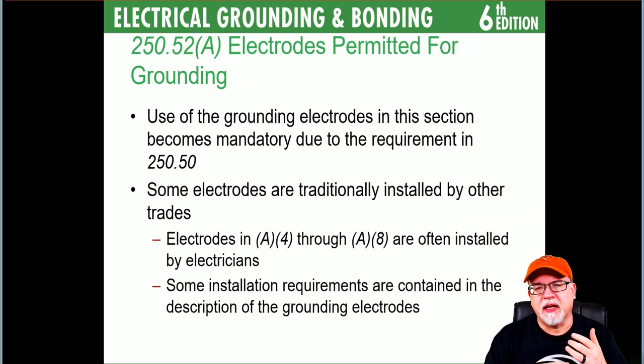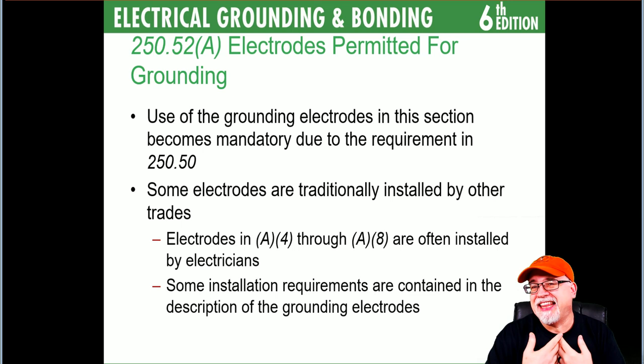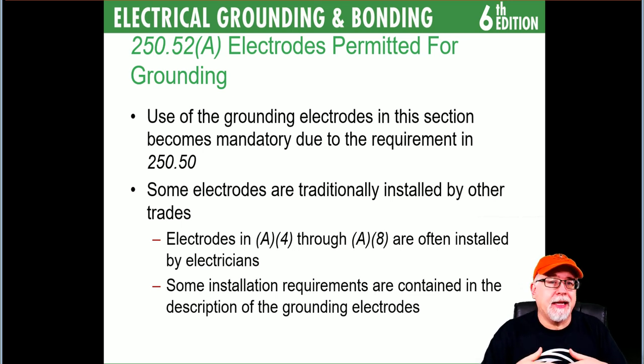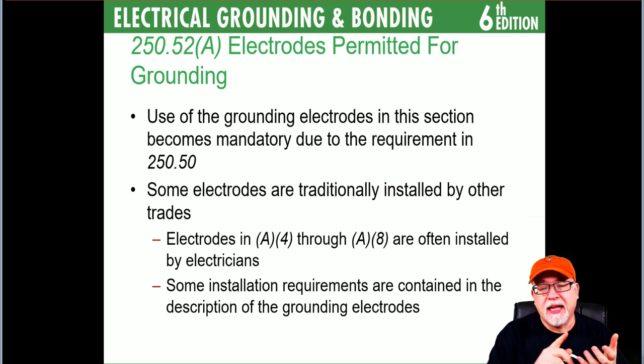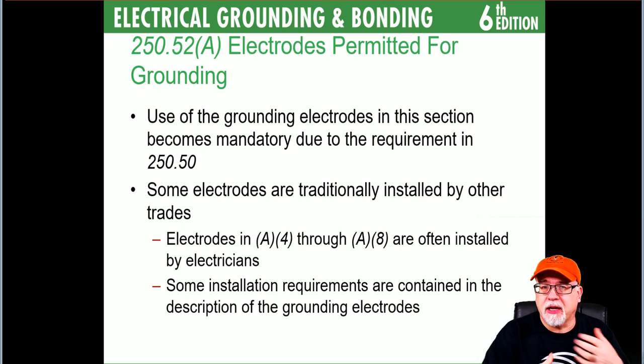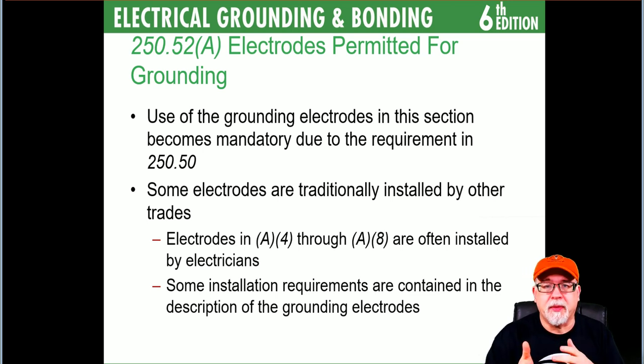Electrodes permitted for grounding: use of grounding electrodes in this section becomes mandatory due to requirements in 250.50. Some electrodes are traditionally installed by other trades — they're inherent to construction. Electrodes A(4) through A(8) are often installed by electricians, whereas A1, A2, and A3 — in-ground steel, concrete encased electrode, or water pipe — are generally installed by somebody else. If it's a water pipe ground, you've got to supplement it obviously.